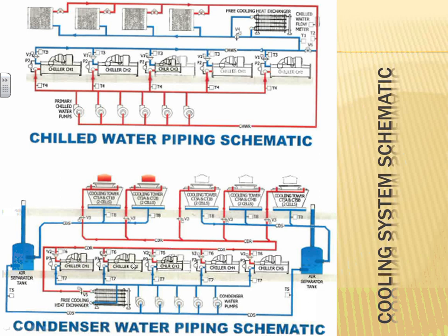But what I'm interested in, all these 5 chillers at the bottom, all these 5 cooling towers at the top, each and every one of them needs a substantial amount of power. A circuit breaker to power it, a conductor or a feeder to control it, and a disconnect to disconnect it. Plus, we have to talk about whether they are going to provide the VFDs on these chillers, or are we providing the VFDs? Typically they do. And all these fans in these cooling towers, are we providing the control system, as in VFDs, typically, or are they providing the VFDs to control all these big fans that are blowing air onto these coils full of hot water and throwing it into Mother Earth?